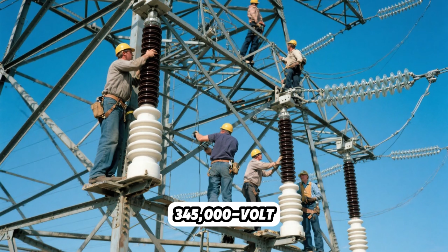Another lineman, a veteran from the 1980s, shared a similar experience that underscores this point. His crew was replacing insulators on a de-energized 345,000-volt line. The line ran parallel to another, fully energized circuit for several miles. They had meticulously grounded their line at the beginning and end of their work zone.